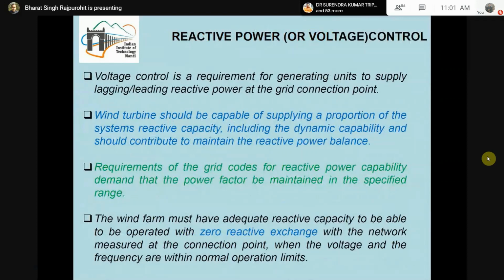The meaning of reactive power or voltage control is that the wind farm or solar farm should be able to have a reactive power exchange with the grid. In ideal conditions, there should be zero reactive exchange, but if the grid wants, the wind farm should be able to inject reactive power or should be able to take reactive power.